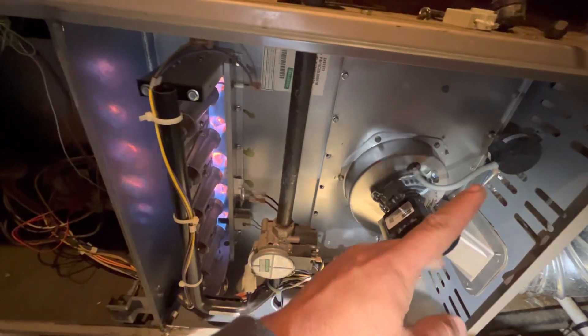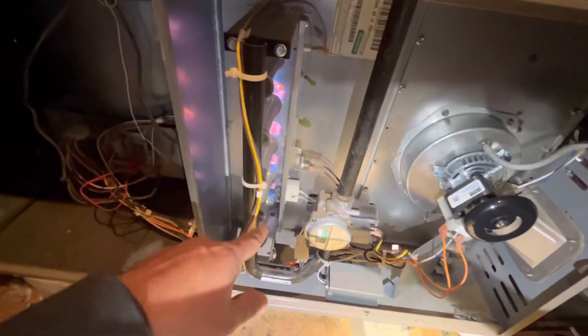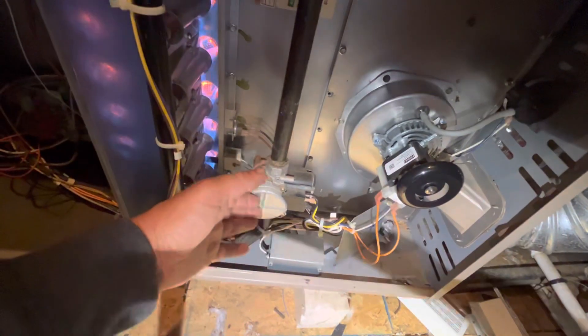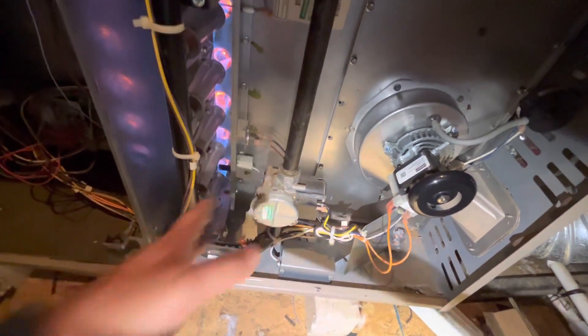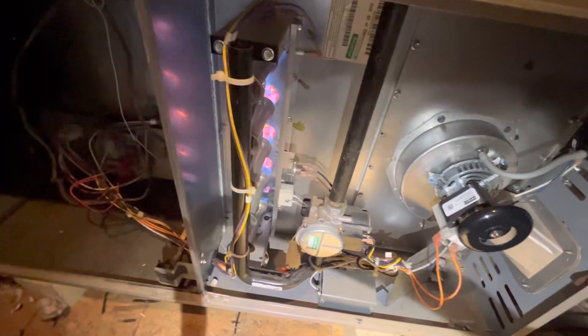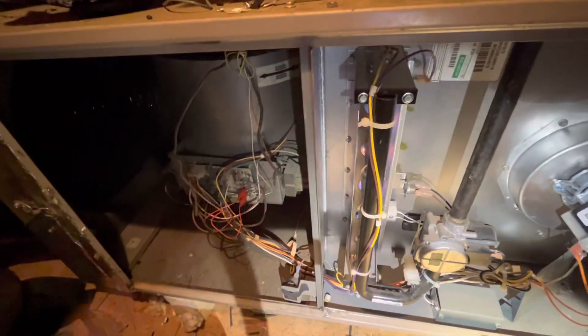So there you go: first the inducer motor turns on, pressure switch closes giving continuity, then the igniter glows, and after that the gas valve gets 24 volts and turns on gas to the burners — that's how it starts to heat your home. Then the fan turns on afterwards.